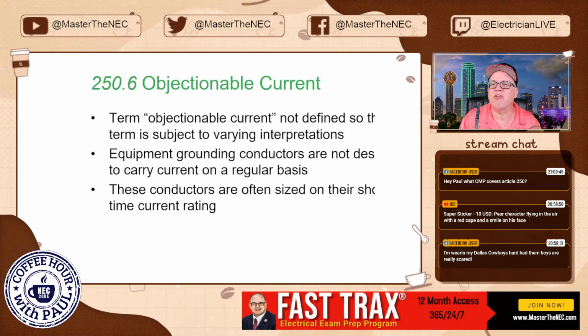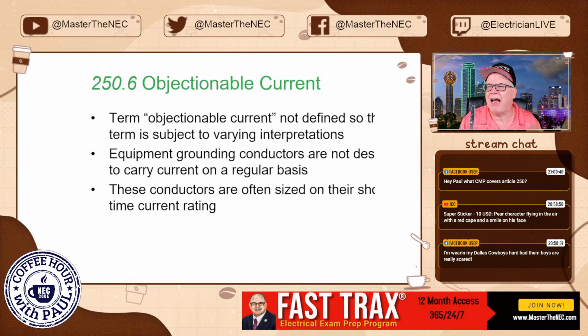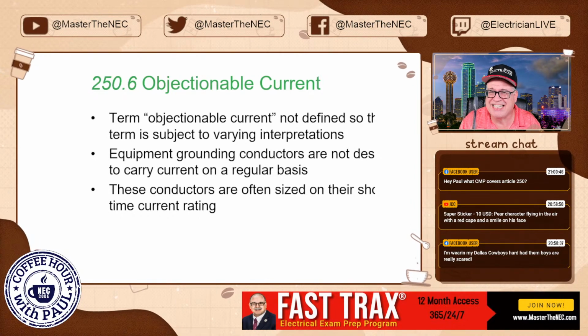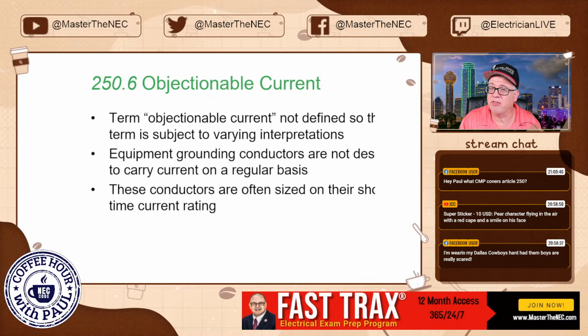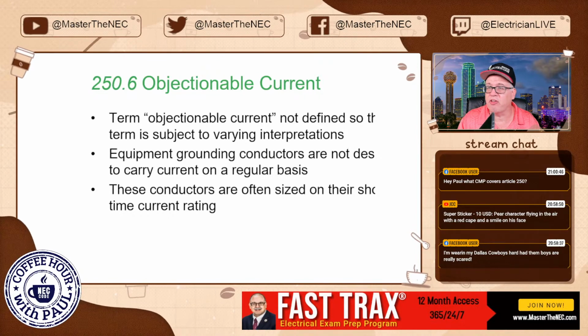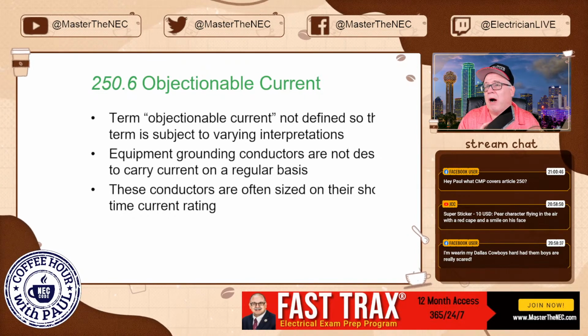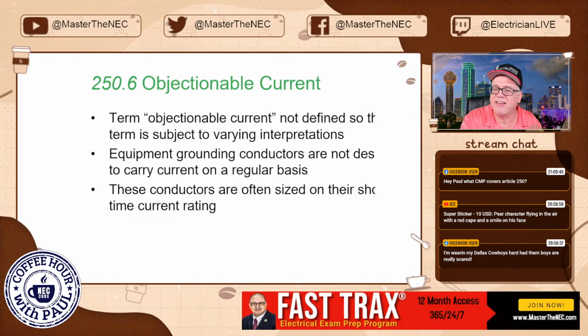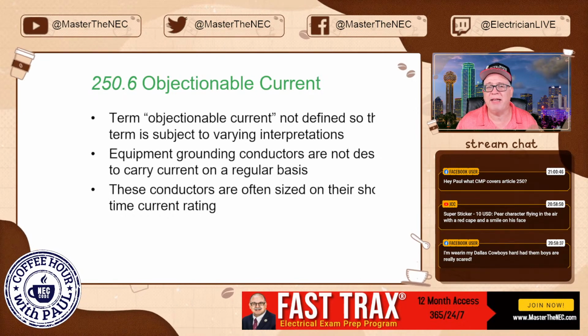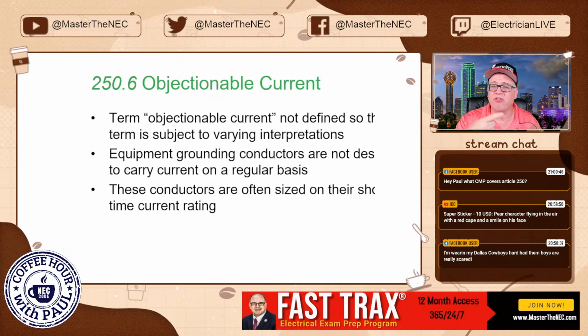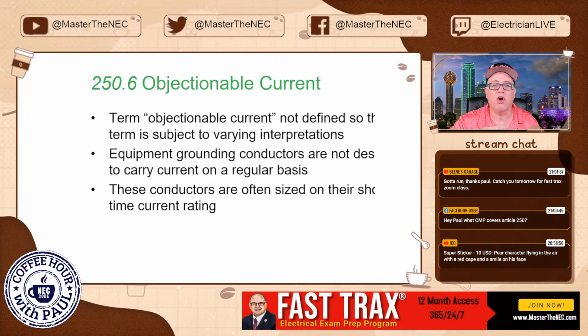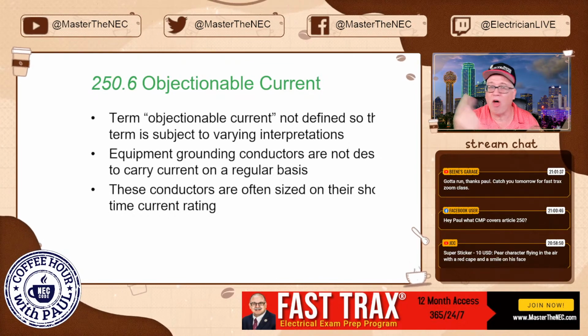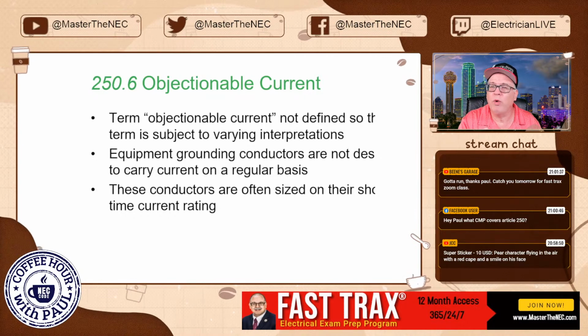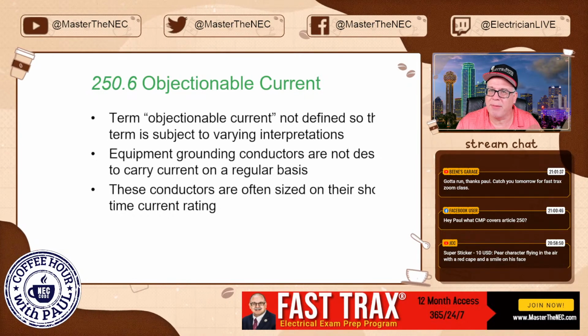Well, that's going to give us circulating current. It means it's going to travel in paths that it wasn't intended to be, because the equipment grounding conductors and all of the metal raceways that you're required to tie together are not designed to carry current on a regular basis. But current will be circulating on a neutral conductor all the time. All the time. So we do not want that current traveling on the metal parts.